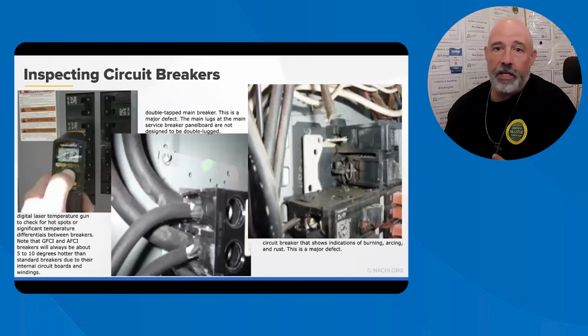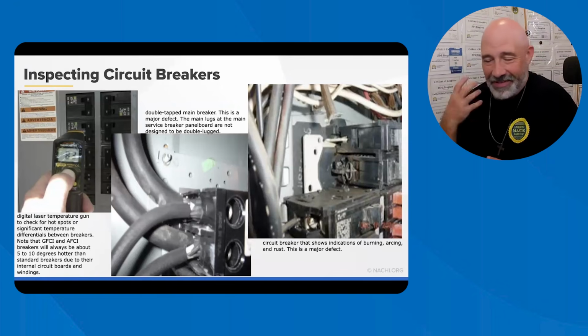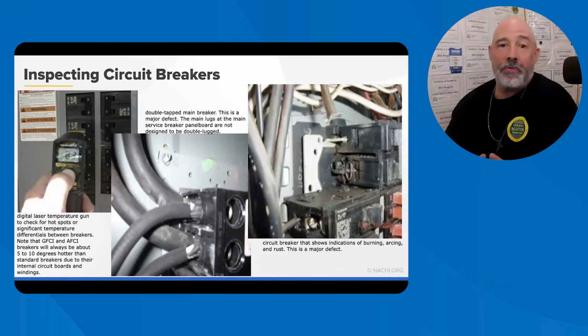The inspector should pay close attention to the following questions and report any defects as such. Does the breaker exceed the capacity of the conductor? Does the breaker have multiple incorrect taps? So those double taps. And I've seen quadruple taps. That's the biggest I've seen. Does the 240-volt breakers have their handles tied properly? I've called that out, and I've gone rounds with people before on that.